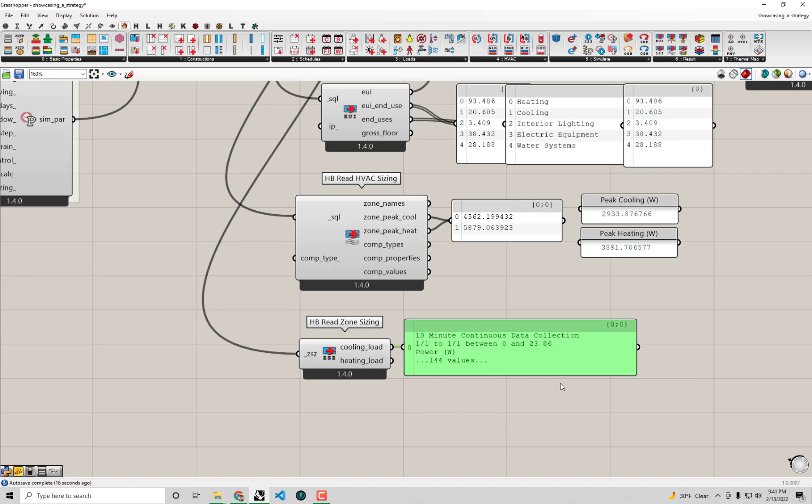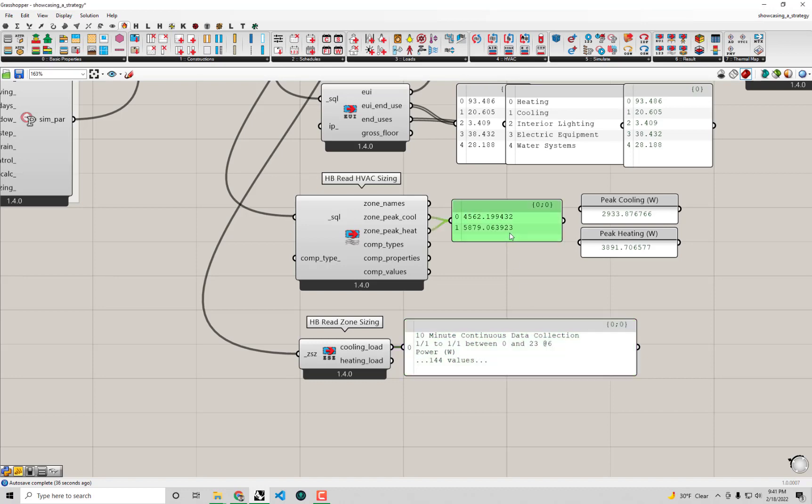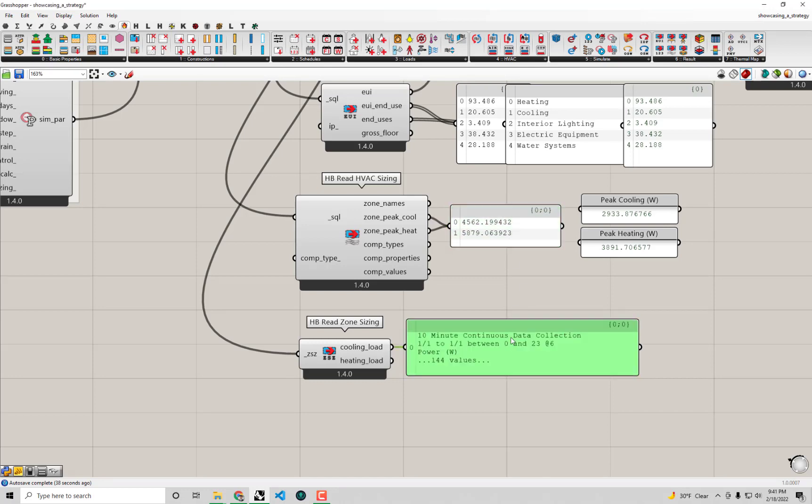In total, we have 144 values. If you were to do the math of the number of minutes times 144, that comes out perfectly to 24 hours. So what this is is a record of the amount of cooling this single-family home needed over the course of that worst-case sunny summer day. It's ultimately from this that we are pulling these specific numbers.